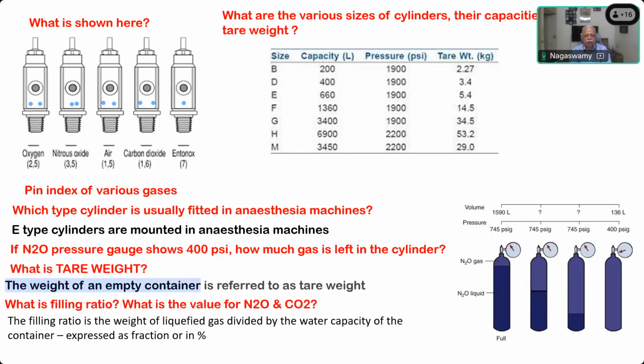Whereas nitrous oxide and carbon dioxide both are stored in the liquid form, which will vaporize to become gas before they are delivered out of the cylinder. So if you fill the cylinder up to its full capacity, there is no room for expansion of the gas, so the cylinder can explode. So to allow some space for the gas to form from the liquid, from the vapor, and get out of the cylinder, you need some space.